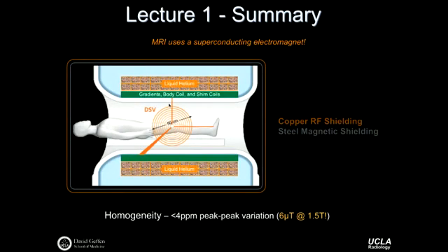And these systems are built to really high tolerance, right? The engineering standards are such that they're accurate to within about 6 microtesla over large volumes in the middle of the scanner. So that's a few parts per million accuracy in terms of the overall field strength.